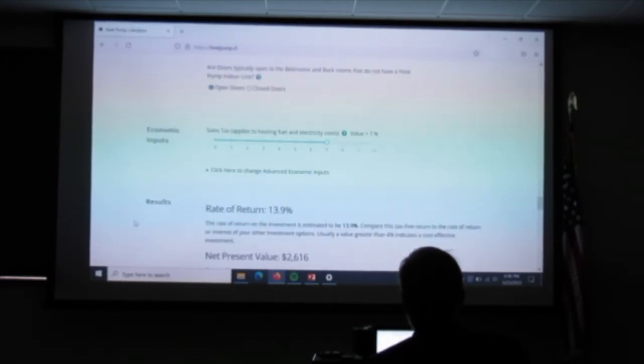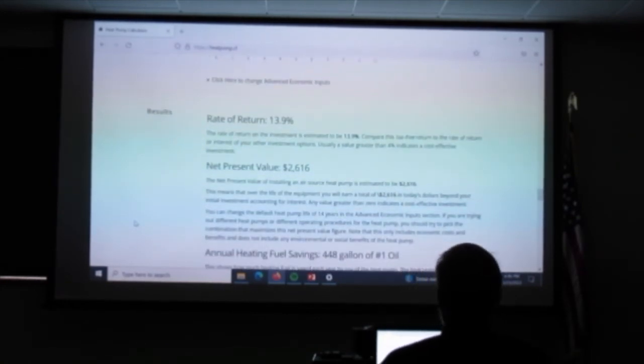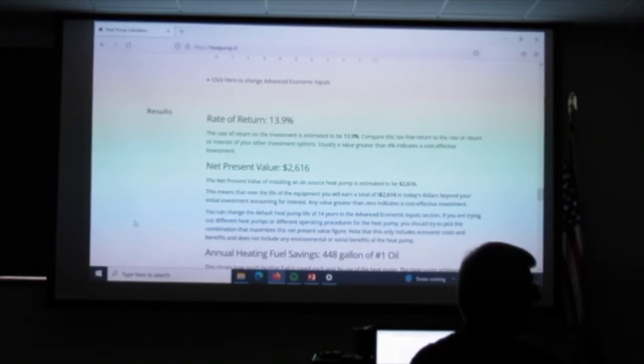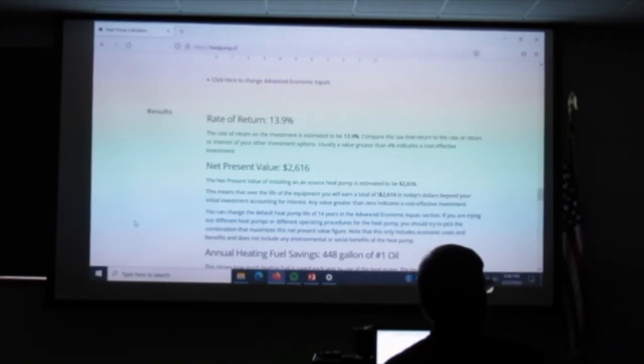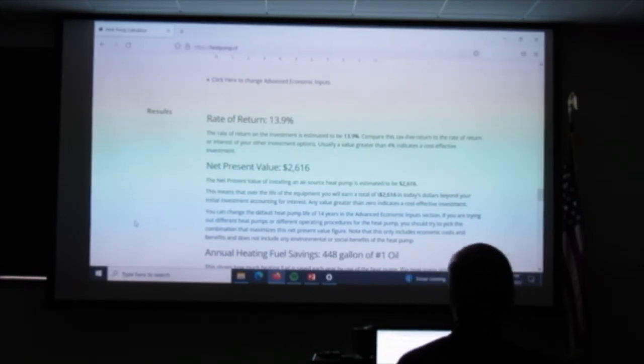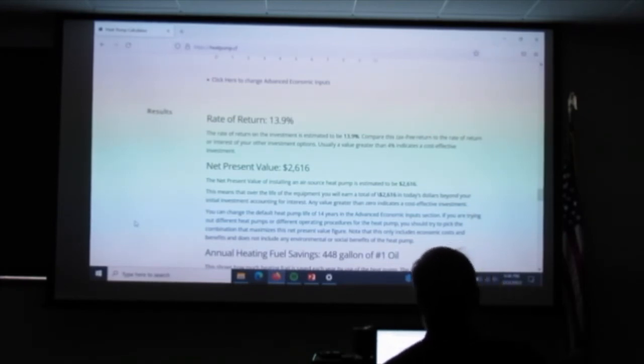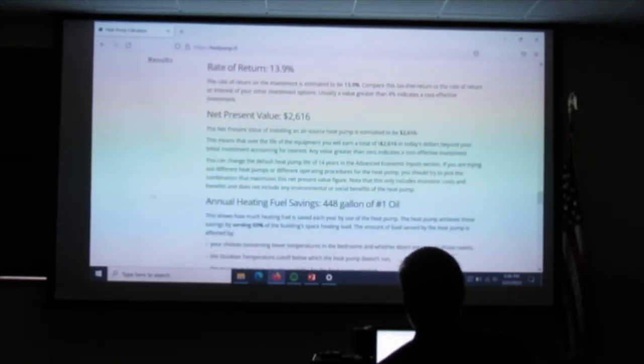You get down here and you hit calculate results. So it's saying for that particular house, putting in that heat pump, you're basically gonna earn 14% on your money over the 14 years of its life. It's just like having it in an IRA or some investment account. That's a pretty nice return. The net present value says after you've paid off all of this, your heat pump, with a little interest, you're still gonna make, in addition to that, $2,600. So it really is showing a pretty good deal. It's saying this particular house is gonna save like 448 gallons of oil a year.